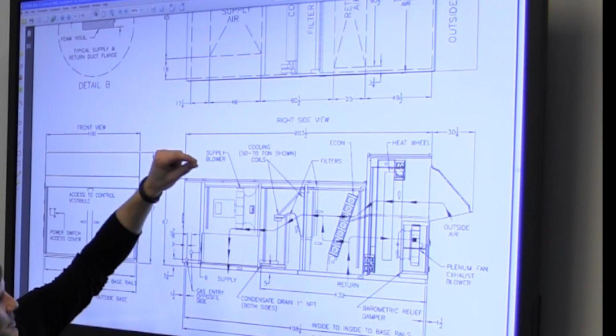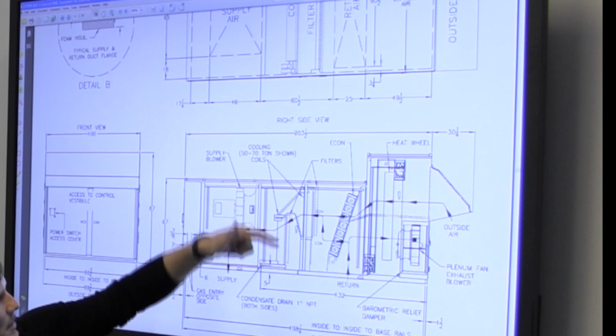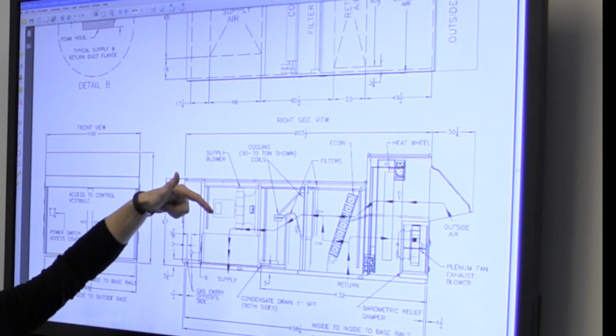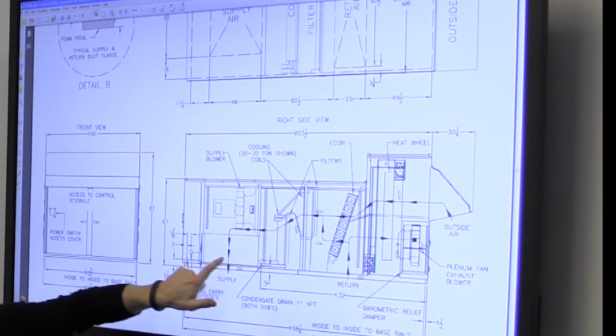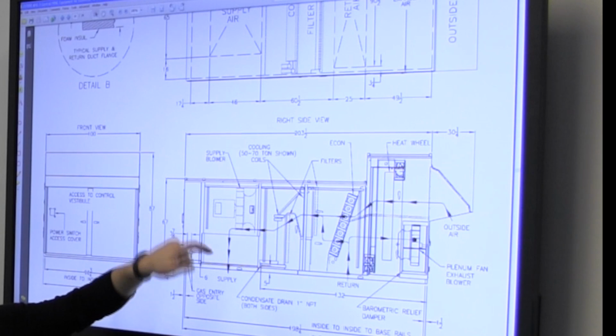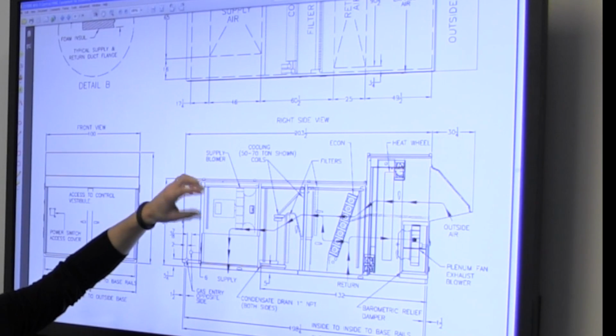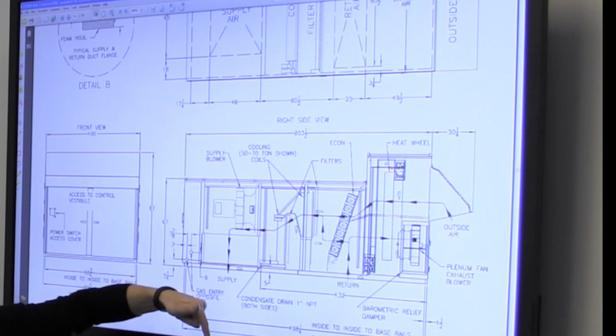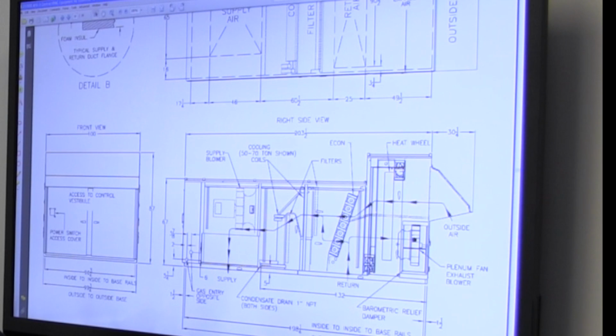You come through those coils, you got a drain pan, then you got your supply fan, and your electric heat is right in here as it blows down. So this supply fan is pressurizing this cabinet, which forces the air down. Goes through the electric heat and out. Again, electric heat is actually on the package units, the heat pumps, not this side.